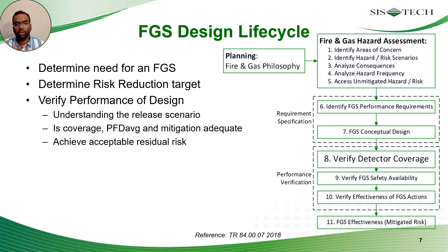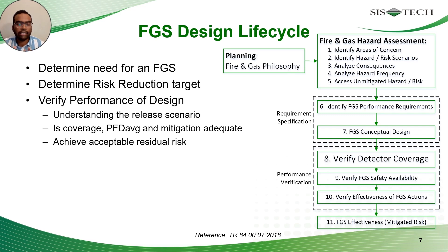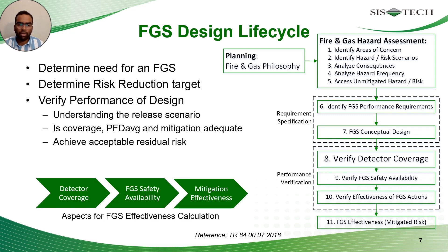When verifying the performance of the design, there are many challenges that the design engineer faces. I have listed three here. First is understanding the release scenario — it is crucial, and you can use simple Gaussian modeling or go for CFD to understand the complexities around it. Second, once you know the details of the release scenario, you look into the detection coverage, hardware PFD average, and how effectively the FGS mitigates the hazard. Third, the residual risk needs to be acceptable per your risk criteria. In summary, the key aspects for FGS effectiveness calculation are detector coverage, safety availability, and mitigation effectiveness.